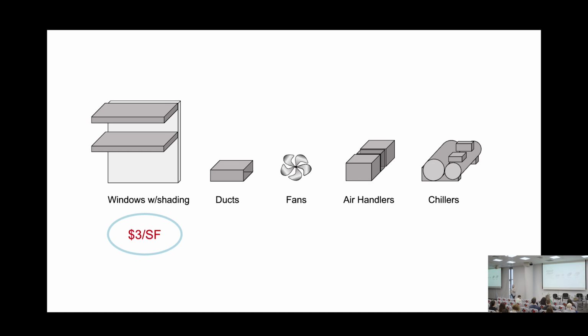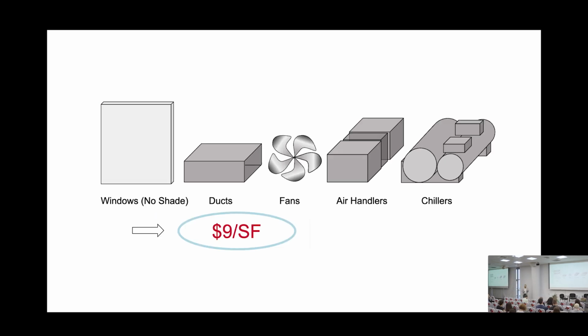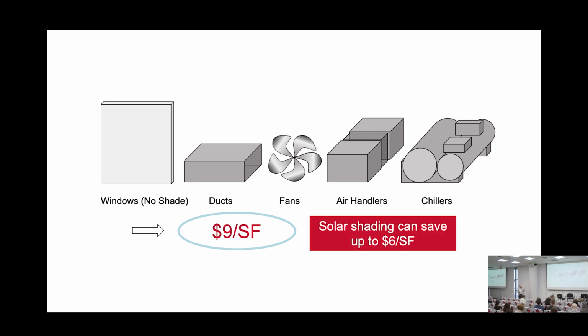Another thing is that if we reduced and removed the shading on the project — yeah, the shading costs about $3 a square foot to install, and the client wasn't happy with that — but once we removed those, we had larger ducts, larger fans, larger air handling units, larger chillers. So really, this was a $9 per square foot cost.